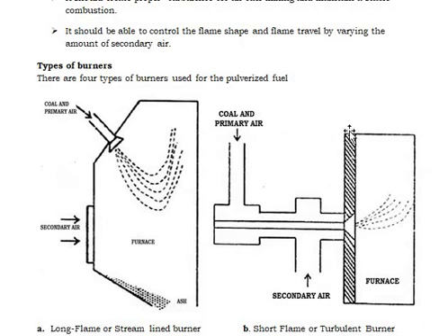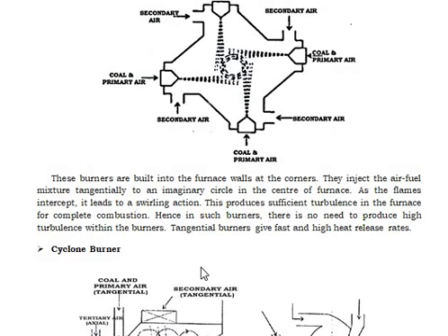Next, you can see the types of burners used for pulverized fuel: the long flame or streamline burner, and the short flame or turbulent burner. These burners are built into furnace walls at the corners; they inject the air-fuel mixture tangentially to an imaginary circle in the center of the furnace, producing flames for complete combustion. Hence, in such burners there is no need to produce high turbulence within the burners.